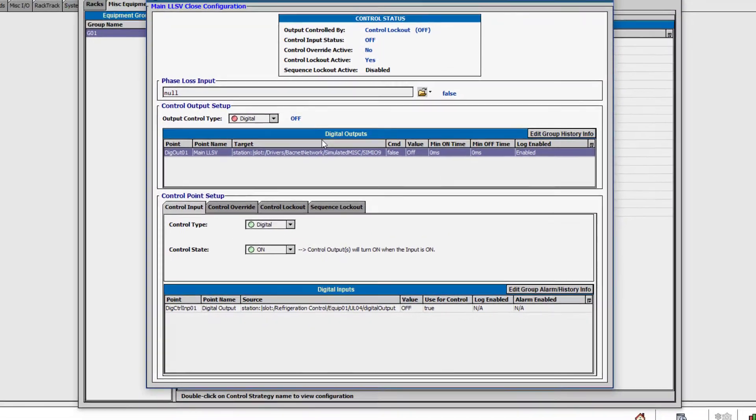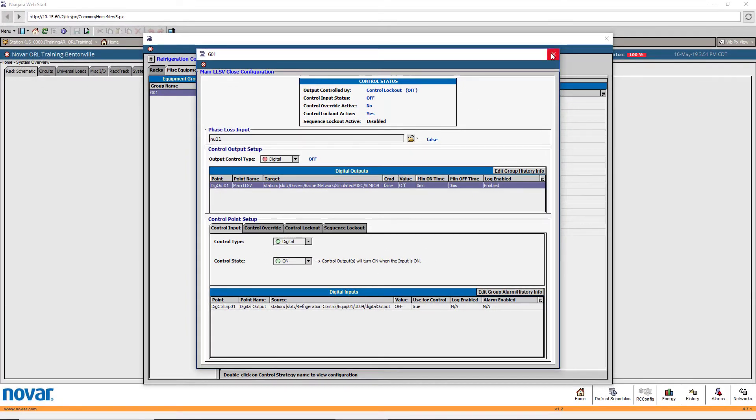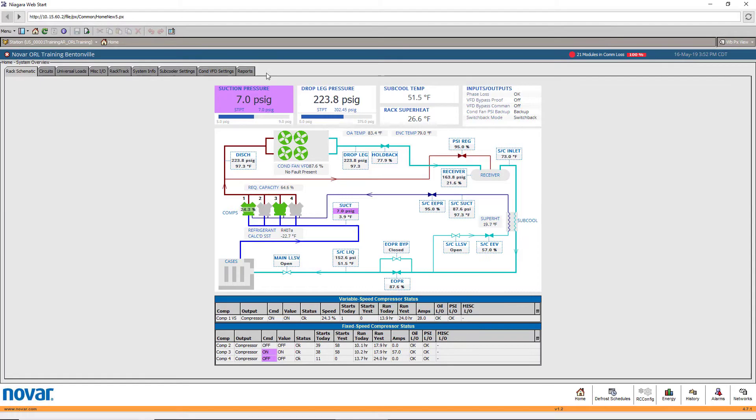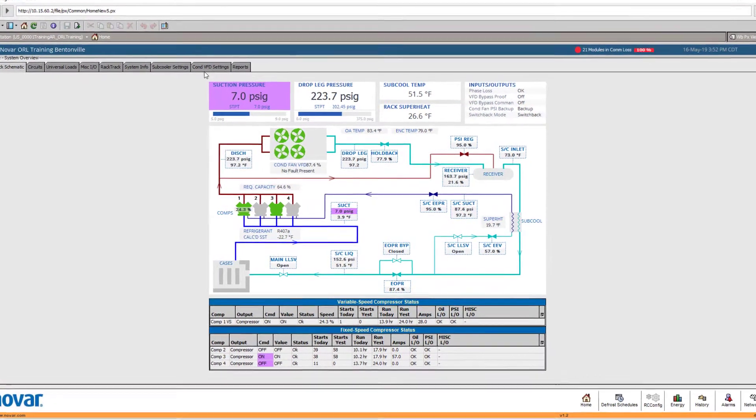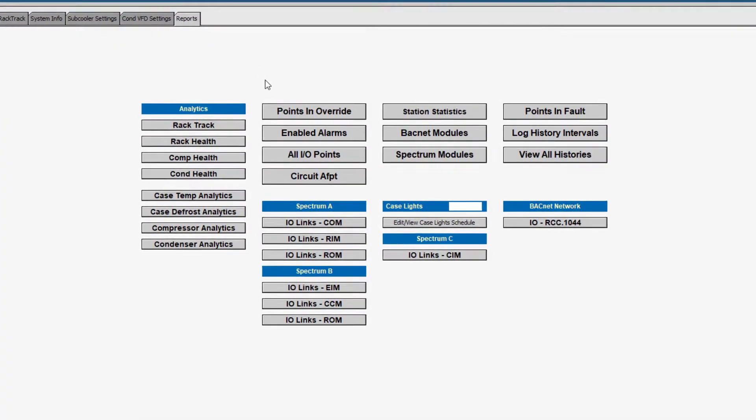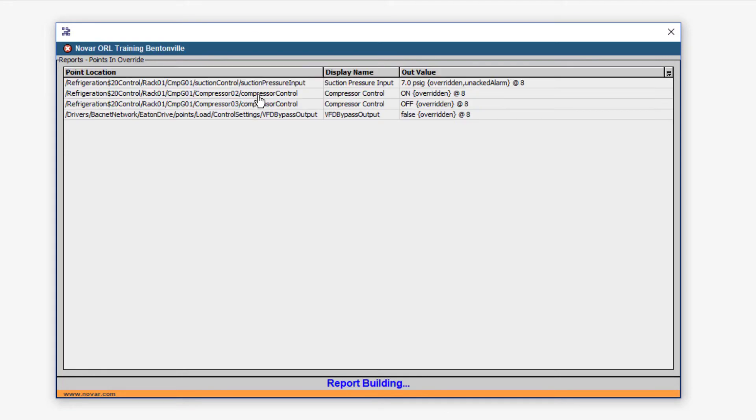A useful tool for monitoring overrides is the points in override report. Here it will show you any points that are currently in override. While you cannot clear any overrides directly from this report, it will show you all that have been forced and the overall health of the system.